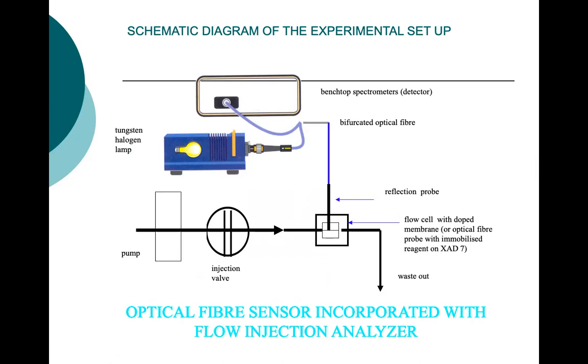And then you can see here, if you have the capacity to look at a normal UV instrument, you see that there are lights shown and so on. But instead of lights shown in an empty space, we can use optical fiber. So this one is a fiber. The light is moving in the fiber. With this technique, you can actually make it portable because the fiber can be detached, it can be connected back.